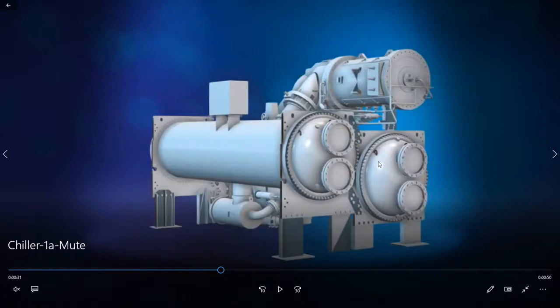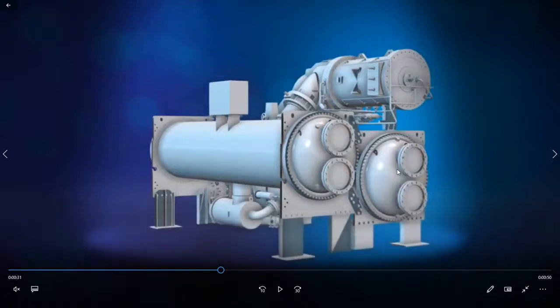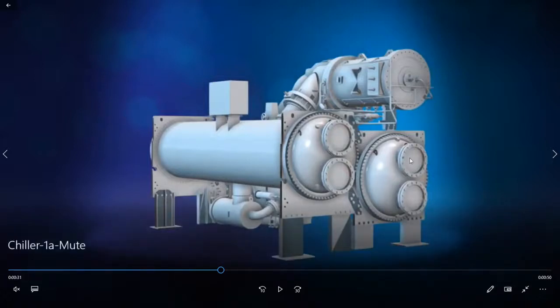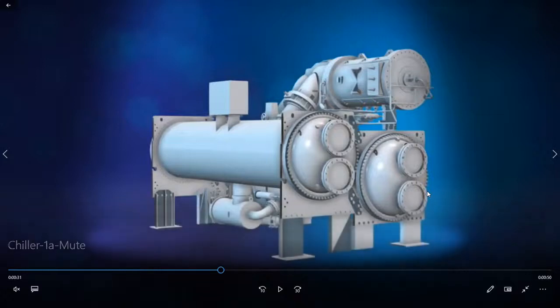And similarly, from the evaporator we will have chilled water going to the air handling unit. So you will have the chilled water coming in, it will be flowing through the pipes, and then the refrigerant will be evaporating on the shell side. The chilled water will then be pumped back to the air handling unit for the cooling of the air over there.